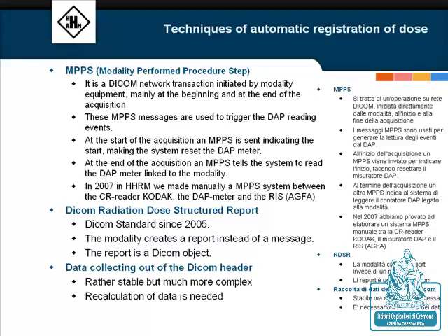When you think about automatic dose registration, and if it's possible to have it on your devices, ask for structured report. This is not a company thing, not Siemens or Philips or Toshiba or whatsoever, it's the DICOM standard. The modality creates a report instead of a message, and that is much more stable.